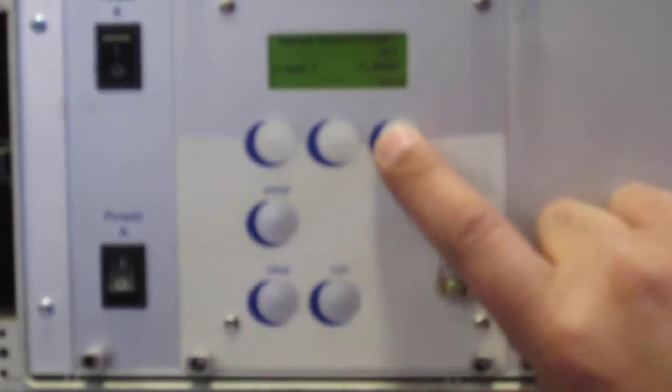It's not going to hold that if I don't say enter. So I'll just say more, and this is rapid switchover in case there's radiation interference around. You don't have to worry about that. It's just if somebody's doing x-rays in a certain area, it automatically has a signal. It switches over, I think 1/5. It takes the time constant down by a factor of 1/5. I forget exactly, but it takes the time constant and switches it over a lot faster, so it switches the measurement output in case there was radiation interference.